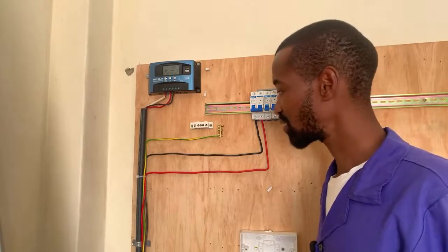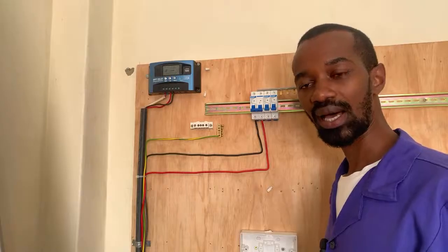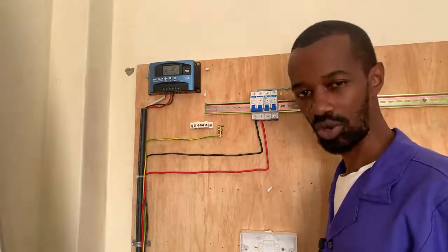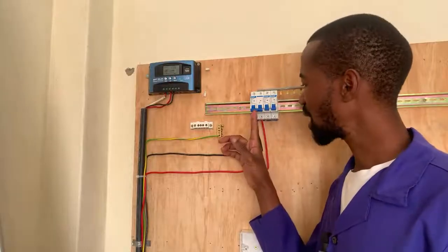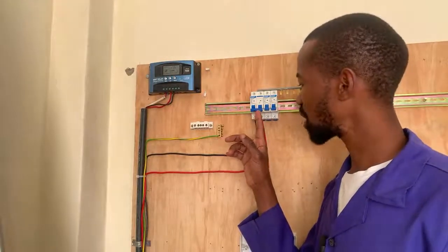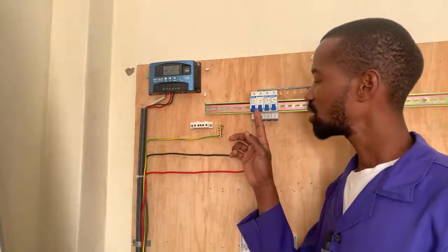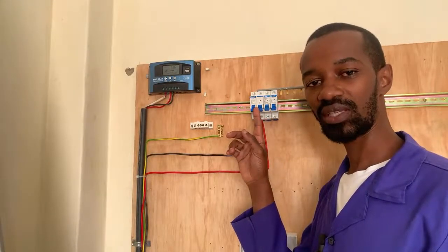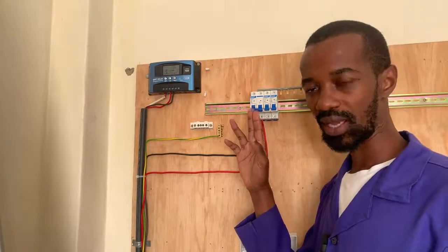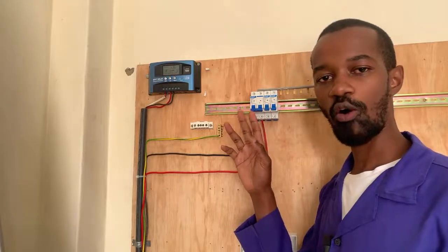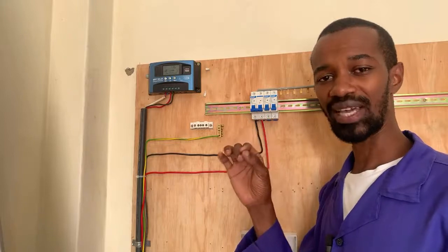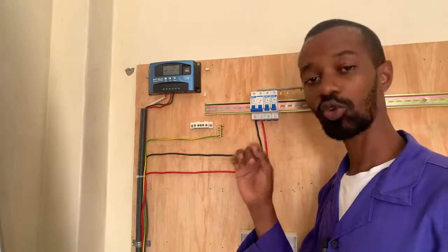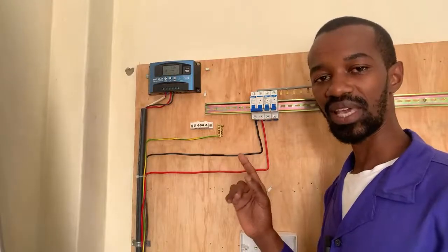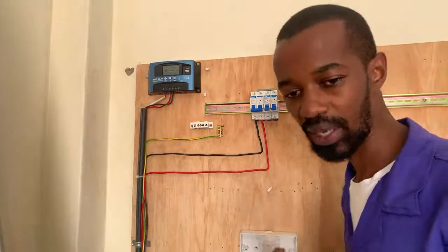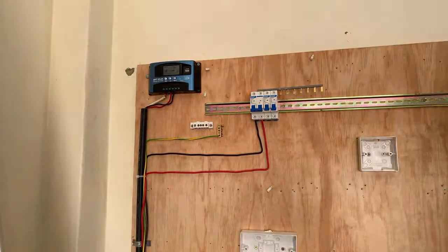In many cases, you find that the neutral does not have a switch or is not disconnected in any manner. The reason why this double pole is switched both at the phase and the neutral is so that you may not switch on the phase while the neutral is off. Why? It will bring about an issue of a neutral that is, we refer to it as floating.